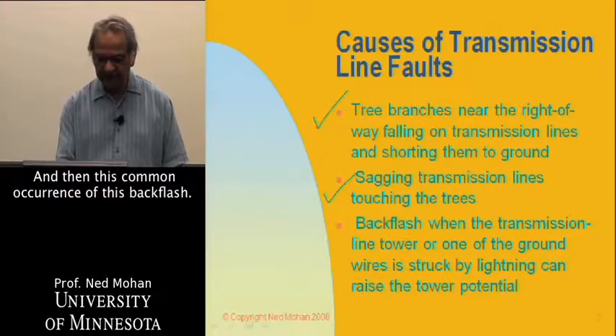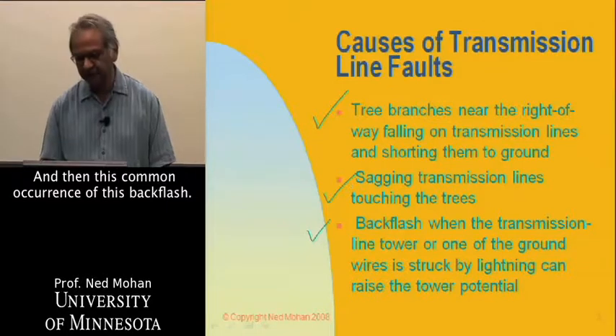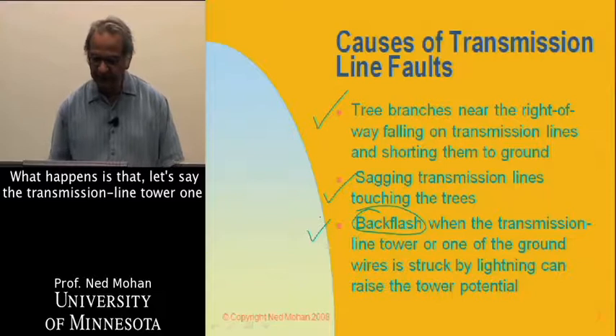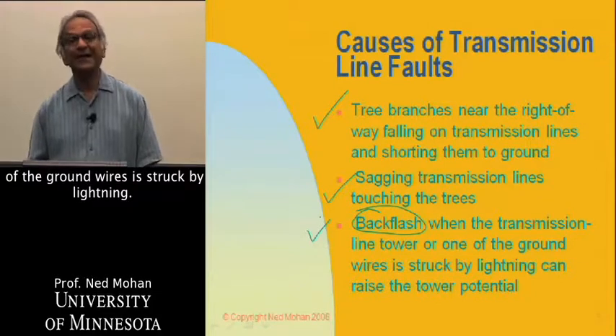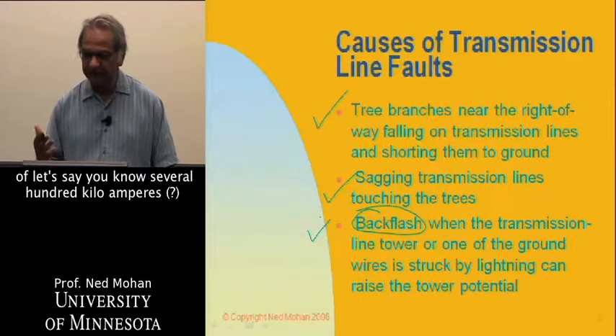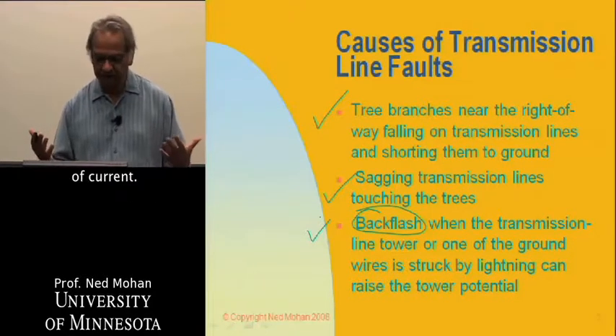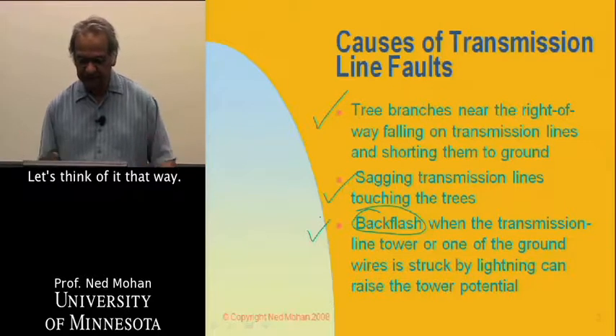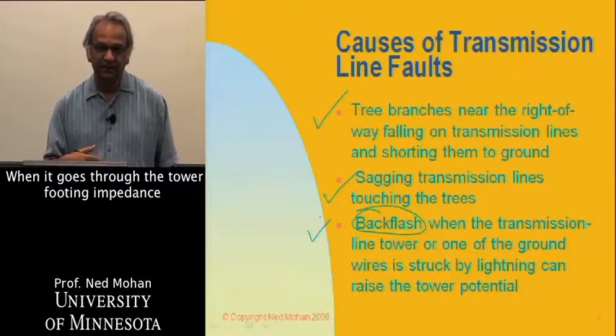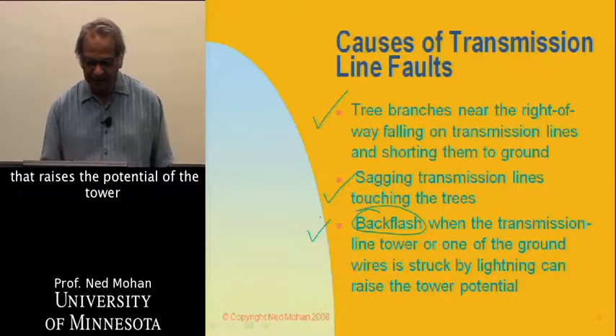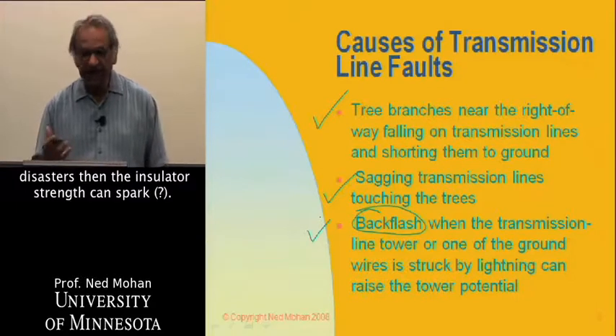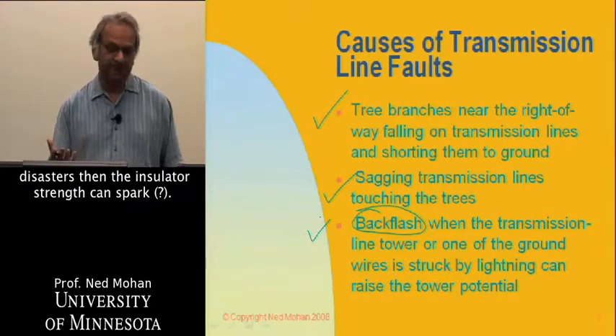And then there's this common occurrence of backflash. What happens is, let's say, the transmission line tower or one of the ground wires is struck by lightning. That lightning consists of several hundred kilo amperes of current. When it goes through the tower footing impedance, that raises the potential of the tower. If there are no surge arrestors, then the insulator string can spark over.